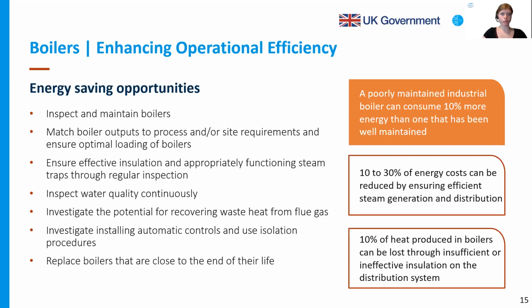It's very critical to match boiler outputs to process load or site requirements, thus ensuring optimal loading of the boilers, especially if you have multiple boilers. And ensure effective insulation. We have always stressed the importance of this. This is heat just thrown into the atmosphere, right? Ensure appropriate functioning of steam traps through regular inspection. We have conducted a comprehensive session to share steam trap management and steam system management best practices.